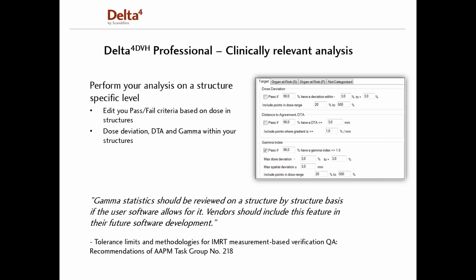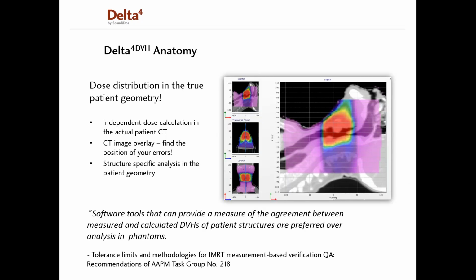A small overdose in the target might not be a bad thing, just as an underdose in the risk organs will most likely be positive, and therefore the Delta4 DVH Professional also allows you to edit your pass-fail criteria differently within your targets and your risk organs, making sure the right criteria are used in the right situations. The publication I mentioned earlier also states that software tools that can provide a measure of the agreement between measured and calculated dose volume histograms of patient structures are preferred over analysis in phantoms.